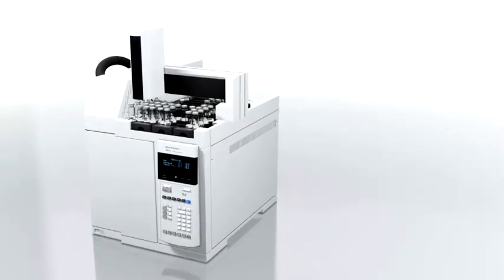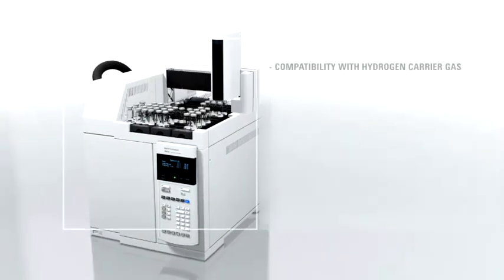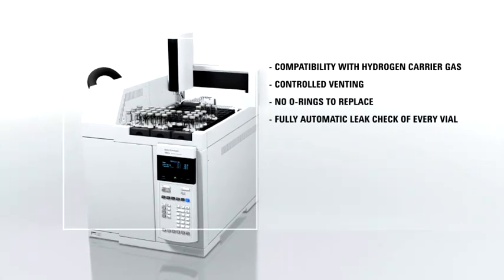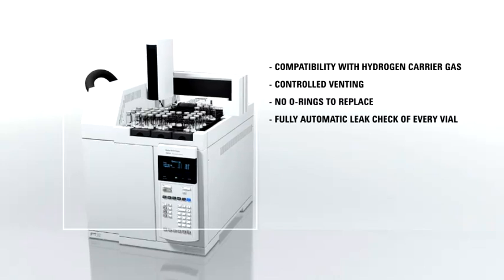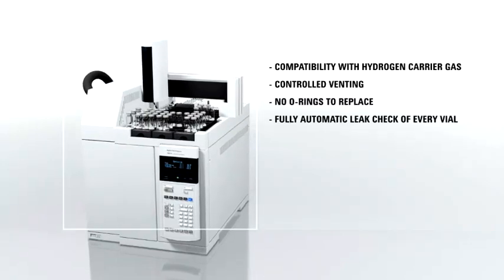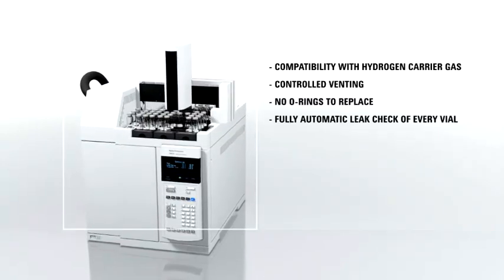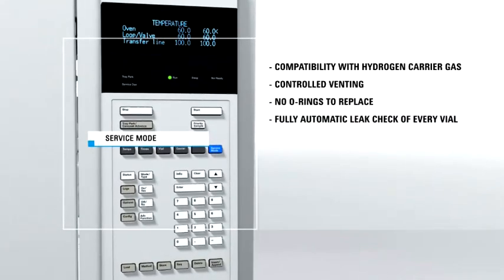The Agilent 7697A Headspace Sampler lowers operating costs and decreases your analysis time. It checks each vial for leaks without time-consuming calibration, reducing the need for re-analysis. It also supports the use of hydrogen carrier gas and offers a one-button full-system leak test for troubleshooting all pneumatic pathways.